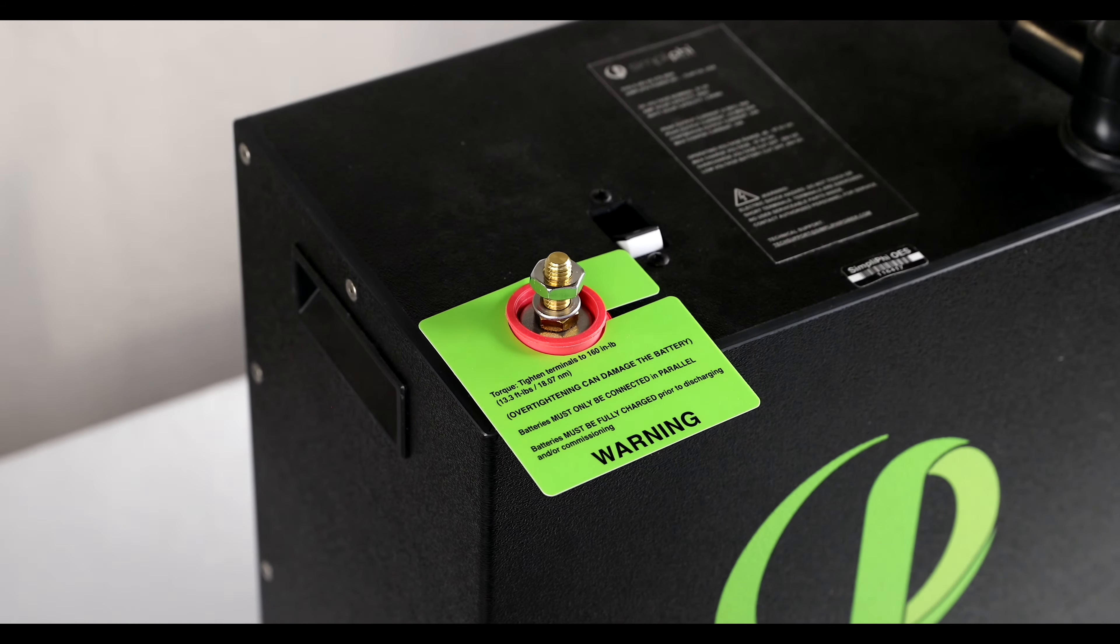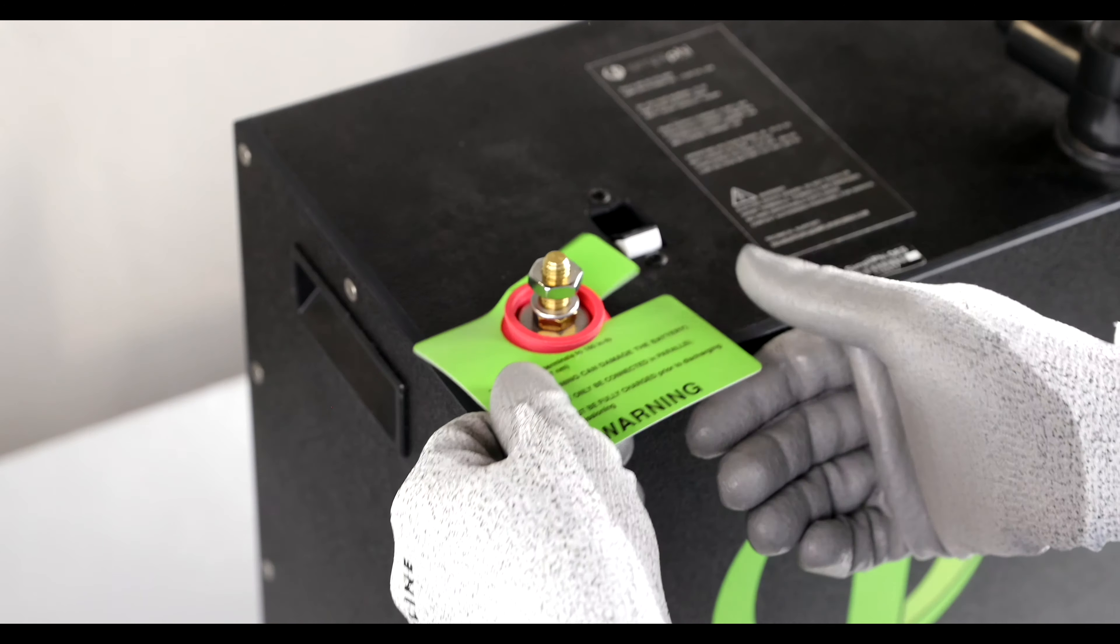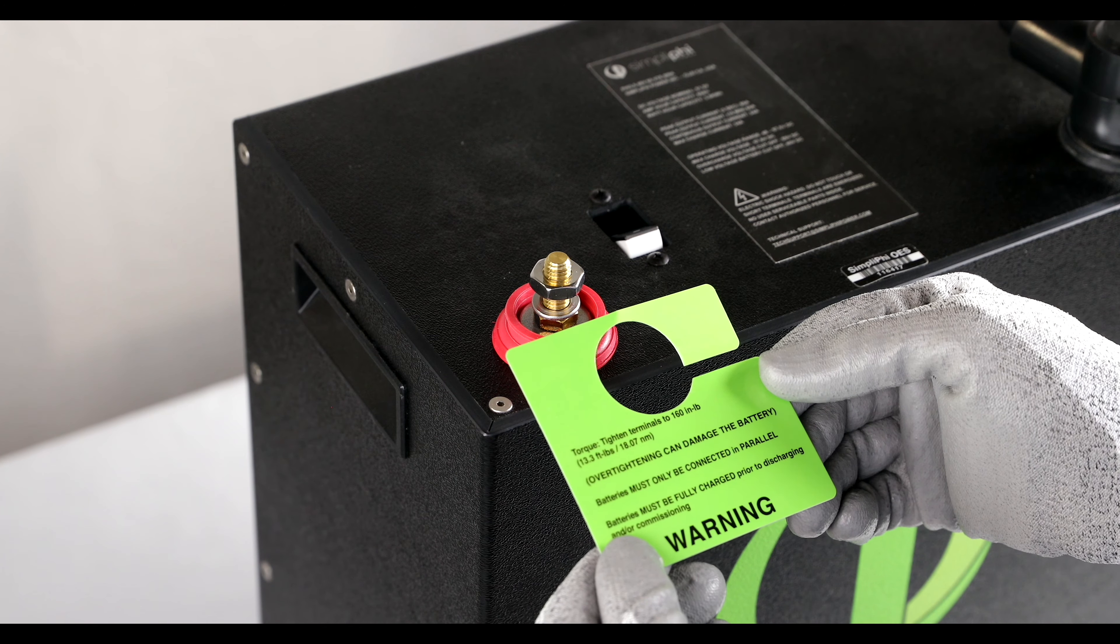Each battery comes with a warning label, and this notes the torque that you should tighten the terminals to. This is 160 inch pounds.